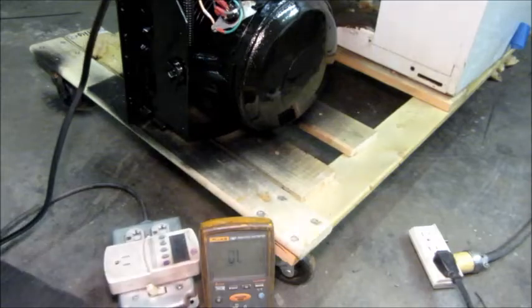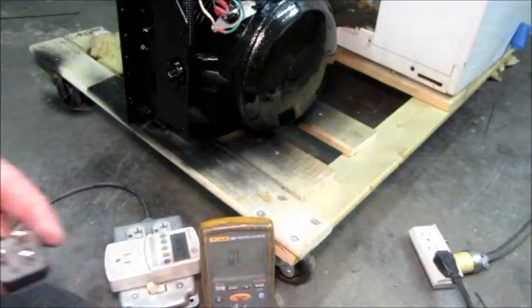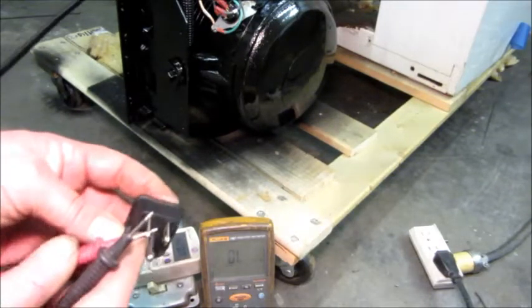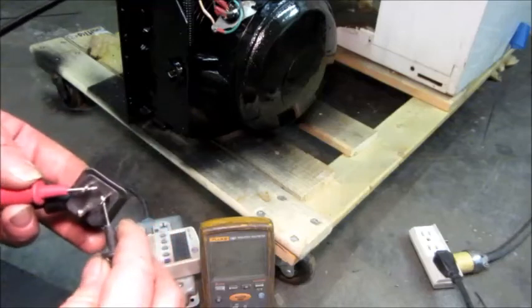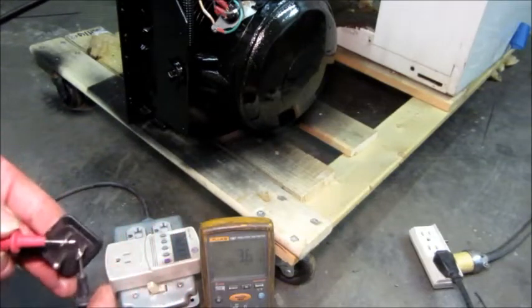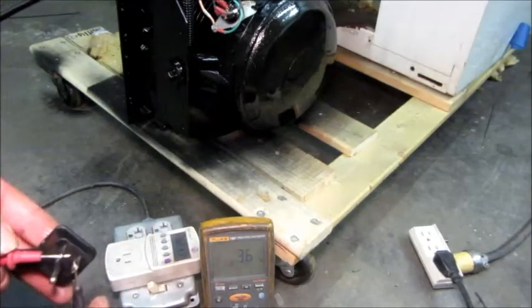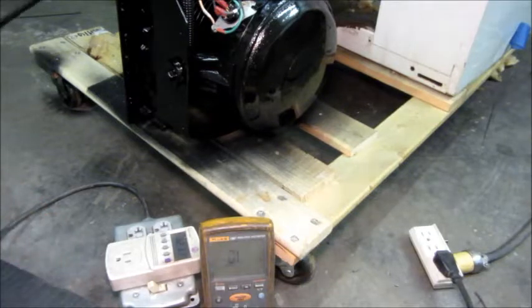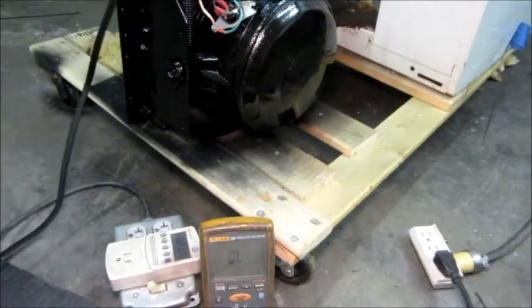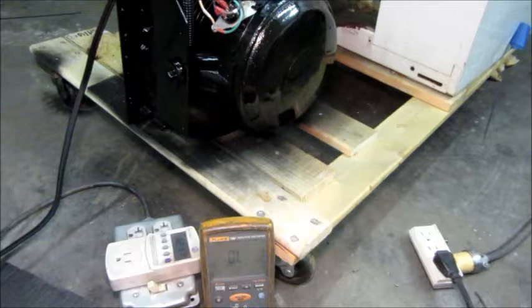So now I've got the thermostat in the on position, and I'm going to measure from one pin to the other. Now we should have a very low resistance. See, 3.6 ohms? That's because we're seeing the resistance of the compressor motor, which is a copper winding in the motor, so there's very little resistance to it.